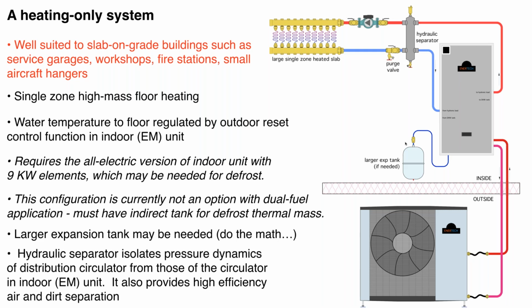A few notes that I put in there. One is check the size of the expansion tank. Now, there is an expansion tank built into the lower left of this indoor compartment. But if you have a very large distribution system with a lot of water volume in it, maybe 100, 200 gallons of water out there, the expansion tank that's built in there may not be large enough, in which case you can add another tank to the system. I showed it there, and the only way you're going to know that really is to do a calculation based on the volume of water that's in the system, what the expected temperature change would be from a no heat condition up to a maximum temperature condition. And there are many ways to do that. There's software, there are charts. If you calculate you need a 5-gallon expansion tank, there is a tapping down here that you can use to add that extra volume expansion tank.